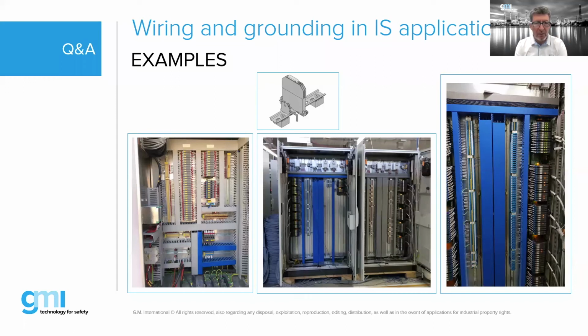In fact, I was trying to look, there was an example in some of these pictures, but now I don't see any example. They're typically kept separate with the blue cable tray. It's easier. But if you have a very small space you have to fit them in, you can, as long as you keep that 50 mil or 50 millimeters or 2 inches apart.